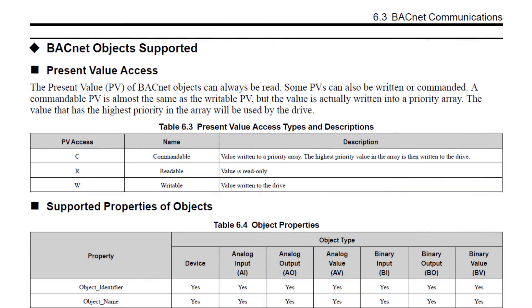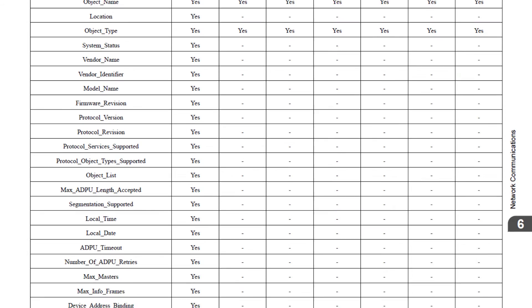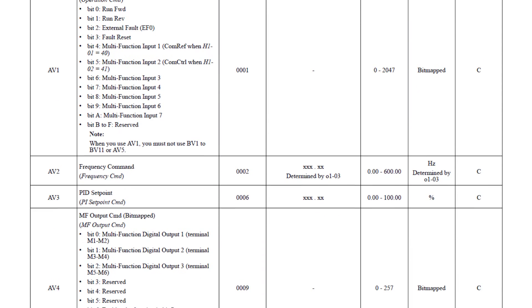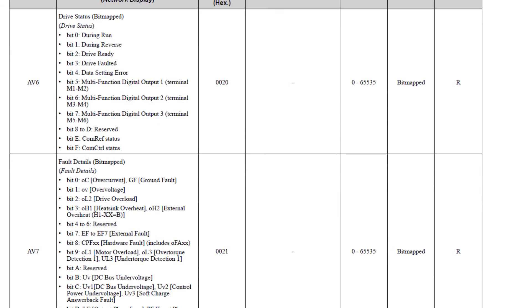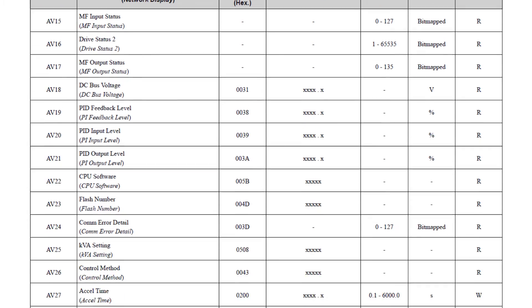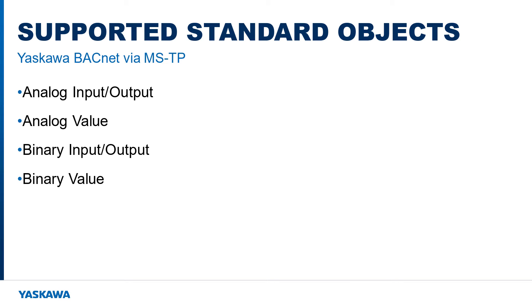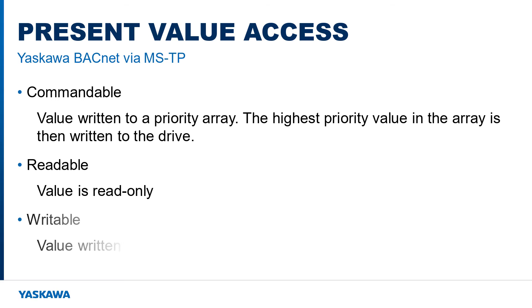Before we highlight some important objects you are likely to view and adjust, we need to explain what an object is. An object is a collection of properties for a specific attribute in a device. BACnet has standard objects widely accepted by most manufacturers, which allows easy integration into building automation systems. Yaskawa supports analog input and output, analog value, binary input and output, binary value, and the device object. While all objects can be read, some present values (PVs) can be written or commanded. Commanded values are similar to writable values but have priority assigned to them, and the highest priority in an array is written to the drive.